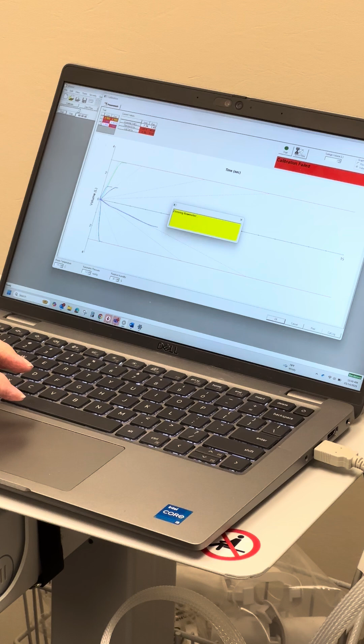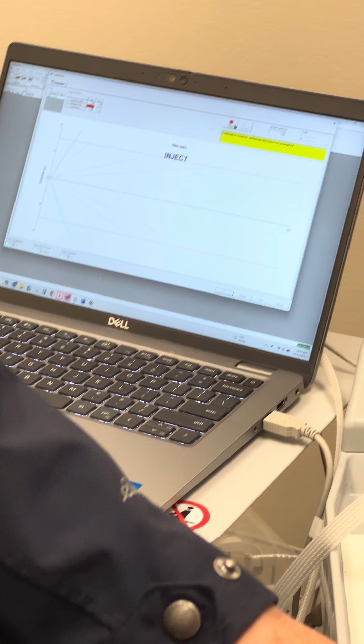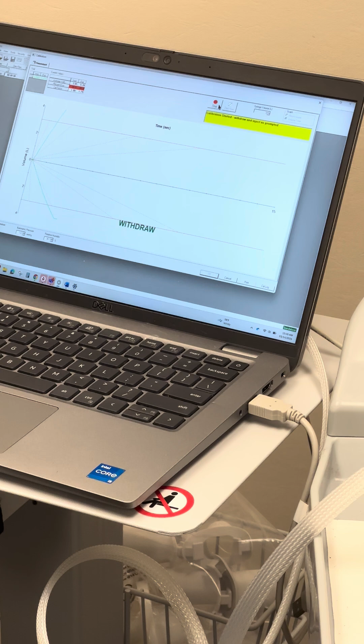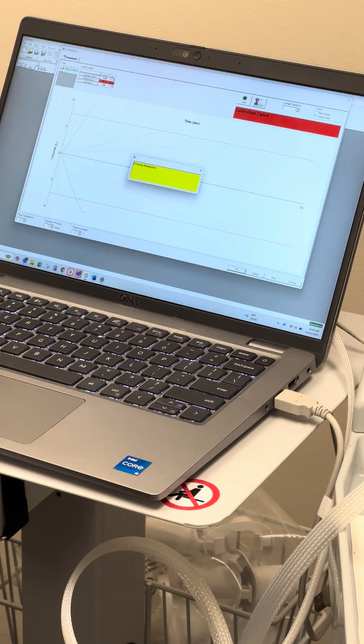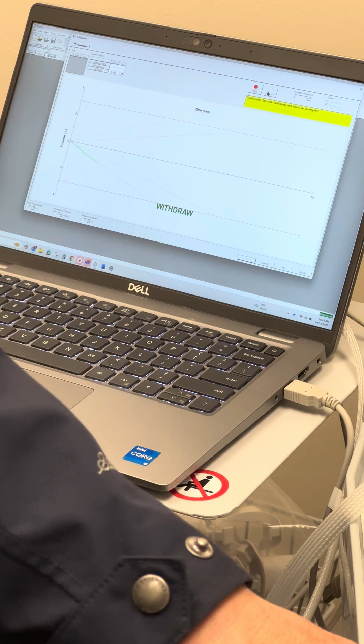So again, I'm going to stop, 0 flow, and then do that reset. And you'll notice this time when I do that medium flow, my flow line is going to extend beyond my 3-liter limit, which is okay because it's relearning or resetting to 3 liters. I'm going to stop. Never hurts to 0 flow. And this time when I start, you'll notice that my flows are right back to the targets where they need to be, to 3 liters.